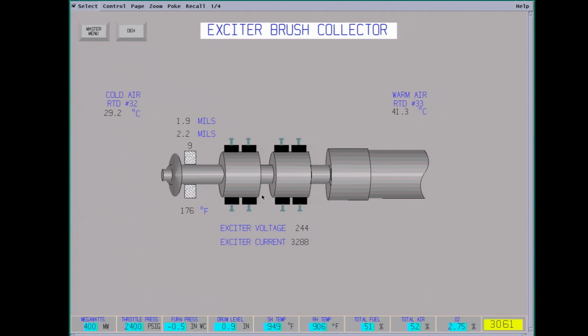Now that's just your exciter brush collector end. Exciter voltage 244 volts. Exciter current 3,288 amps. This looks for vibration and temperatures. You have your air coming in and warm air coming out. These are carbon brushes. Once a week you have to go through, check them, replace brushes as they wear. It's in the, used to be the exciter housing. They used to have a mechanical exciter, but it was changed to solid state. It's a little more efficient, less wear.